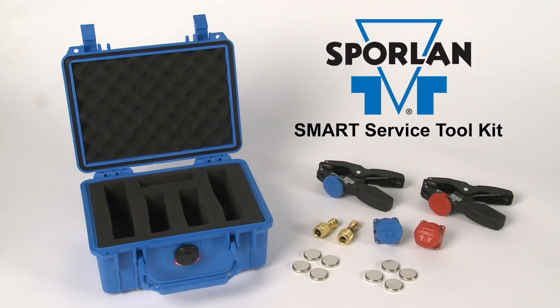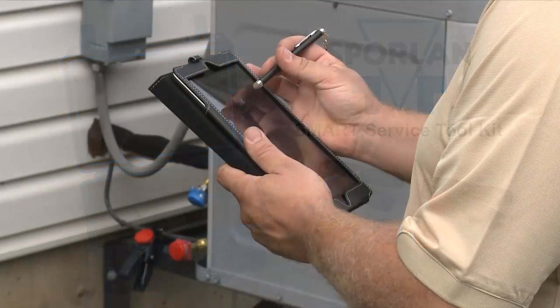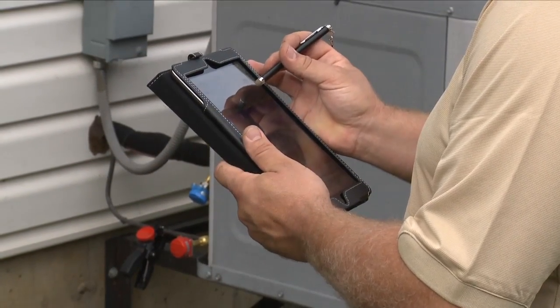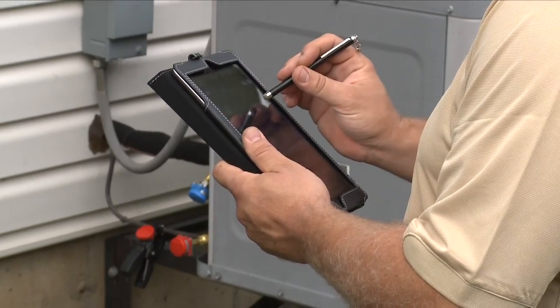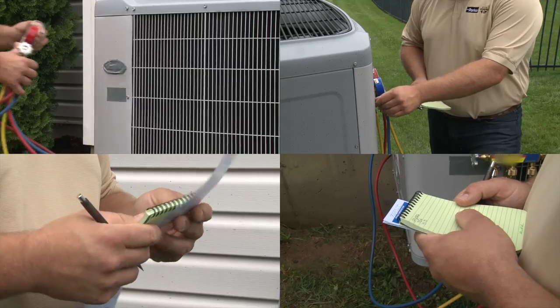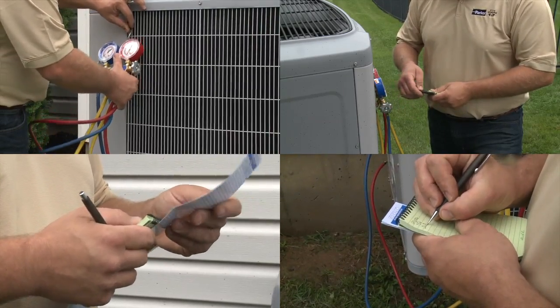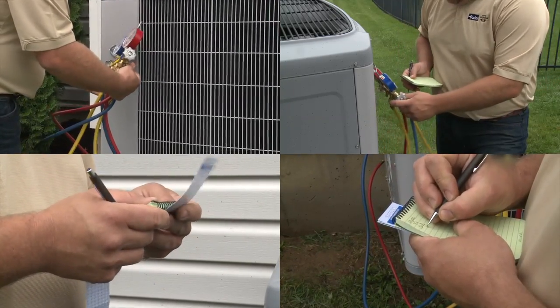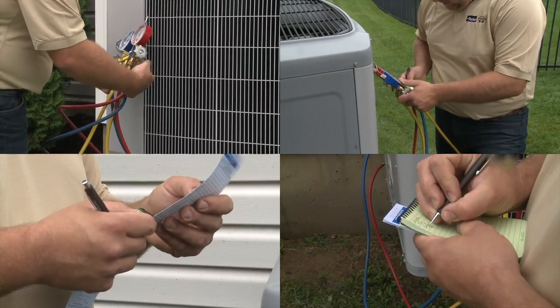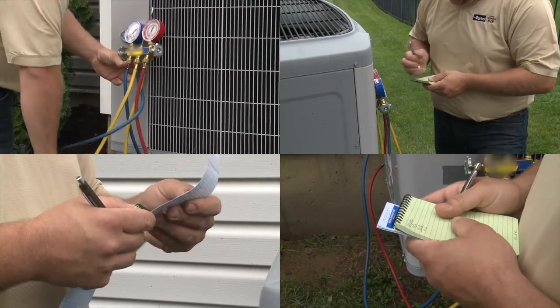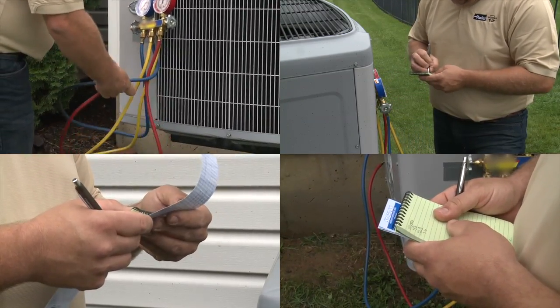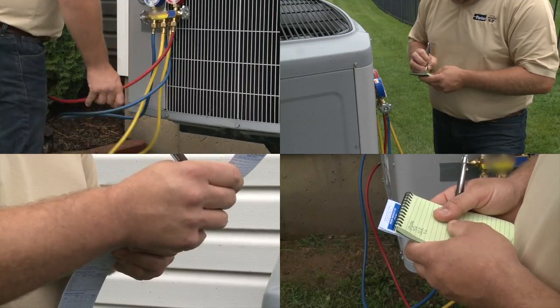The introduction of the Sporlan SMART Service Toolkit made diagnosing and servicing HVACR faster, easier, and more accurate. Until Sporlan SMART Service Tools, calculating superheat and subcooling required cumbersome equipment, writing down temperature and pressure readings, converting pressure readings using a PT chart, and finally, subtracting totals to arrive at actual levels.